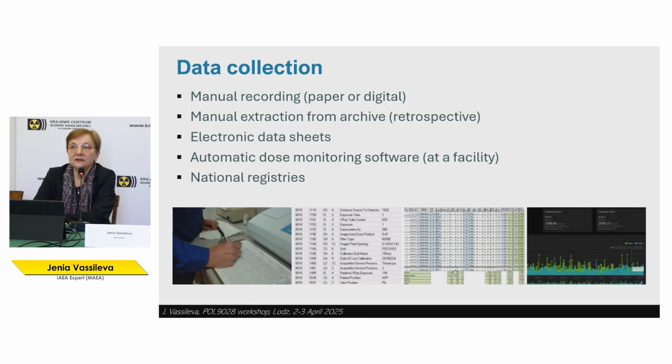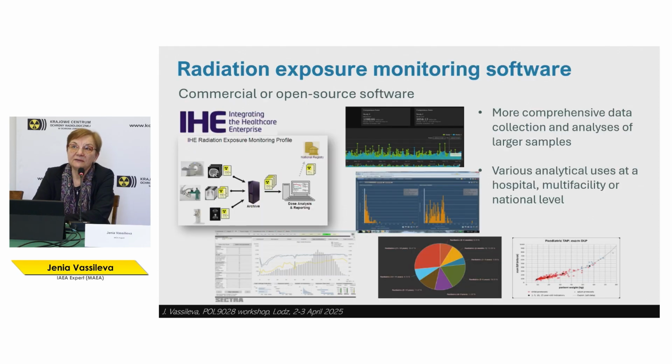That's why the modern approach is automatic dose monitoring, and it's available nowadays. There is standardization with the initiative of the vendors called Integrating the Healthcare Enterprise, with the so-called REM, Radiation Exposure Monitoring Profile, that standardizes and makes it possible to collect data from various vendors in a vendor-independent manner.